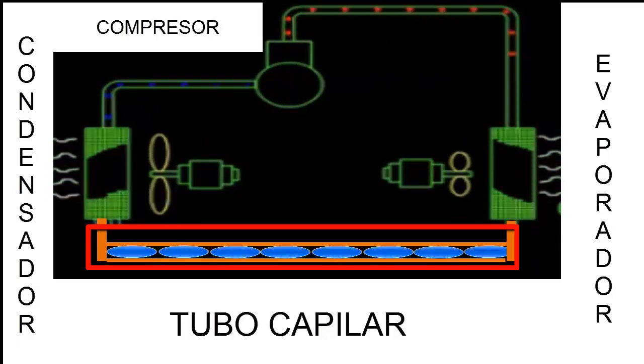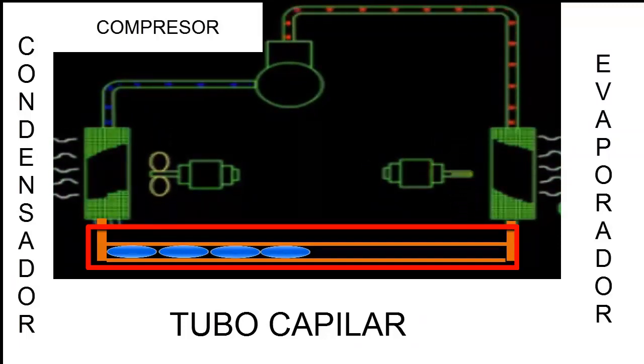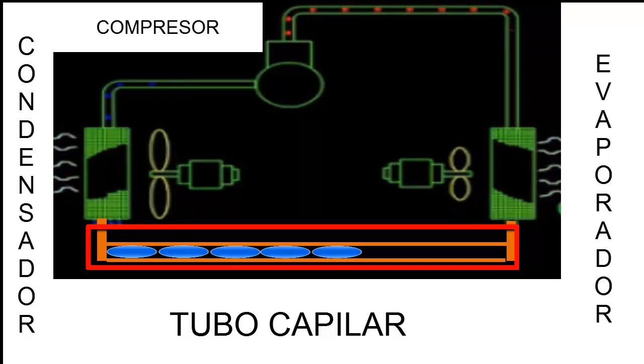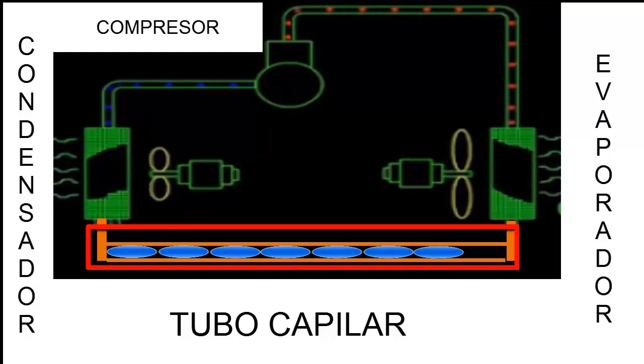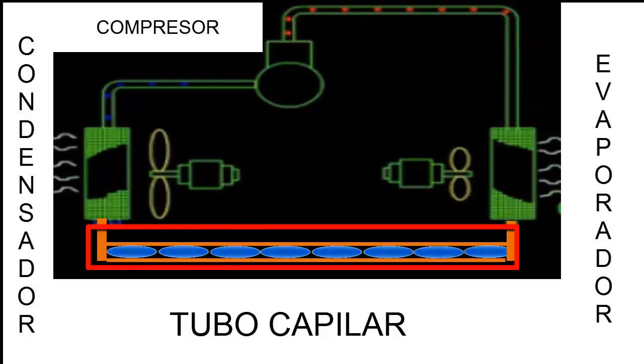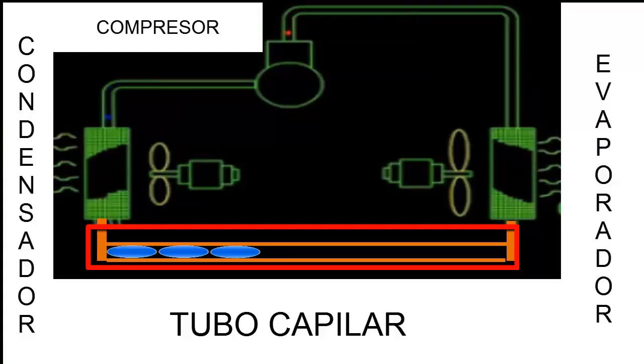What happens when we place a larger diameter than the normal value? Diameters affect especially low pressure. It does not mean that high pressure is not affected. High pressure will also be affected. Of course, it will be affected. But mostly we are going to see the failure in low pressure. Of course, by placing exaggerated diameter values, it will reach certain values where the high is not achieved, because there's no restriction. We are talking about variations of slightly larger or slightly smaller diameters.